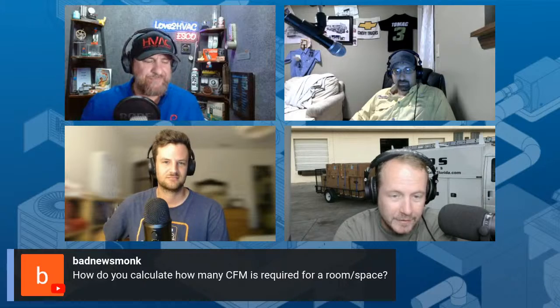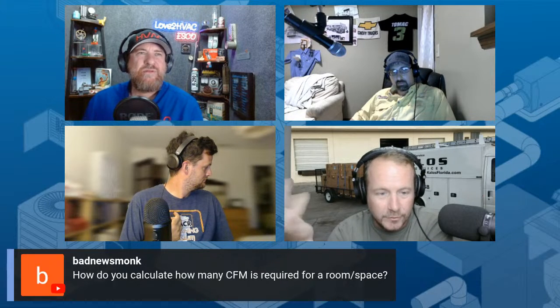The right answer is you first have to do a room-by-room Manual J, and then you have to do a Manual D to calculate how much CFM based on that. But if you already know how many BTUs are required in each room from the room-by-room Manual J, you can take your total system capacity and your total system airflow and just divide it out to figure out each room's airflow. Pretty easy at that point.